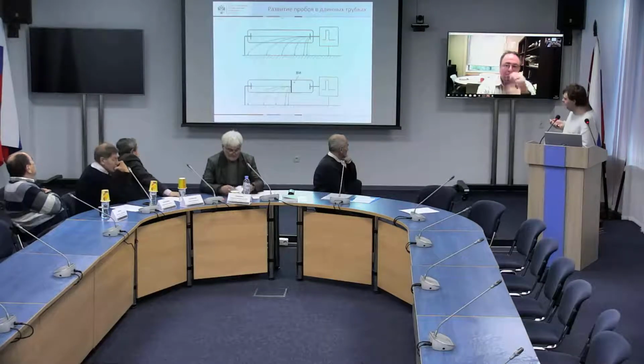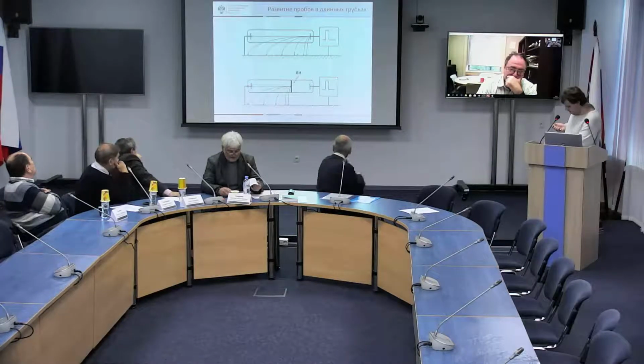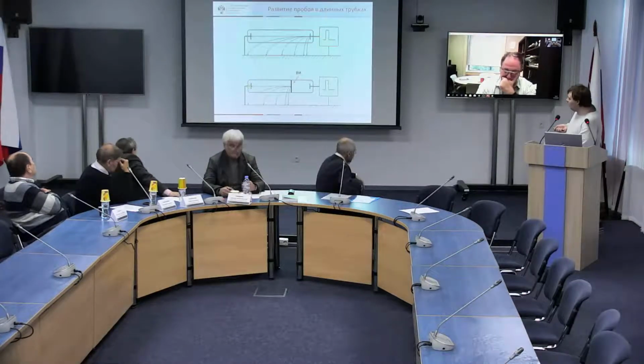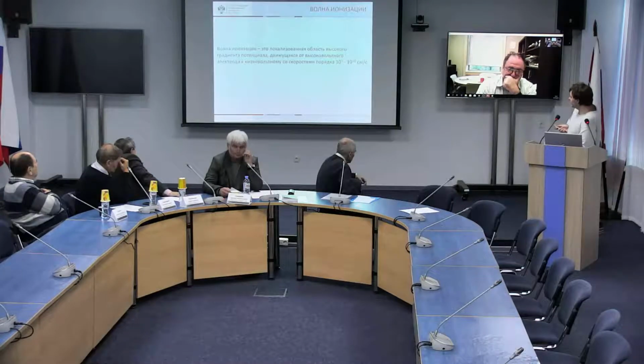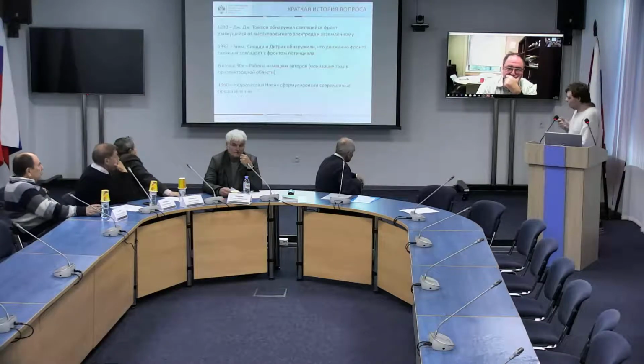At first, the primary breakdown occurs between the electrode on which high voltage is applied and the nearest part of the tube wall. Then, an ionization wave starts to spread from it in the direction of the grounded electrode. Gas is ionized and the entire tube breaks down. The ionization wave is a localized high potential gradient moving from the high voltage electrode to the low voltage one at the rate of 10^5 to 10^10 centimeters per second.